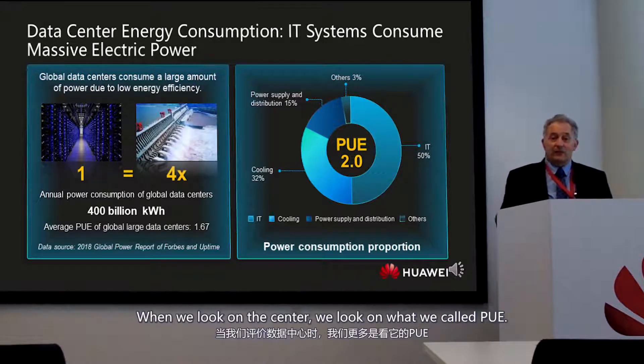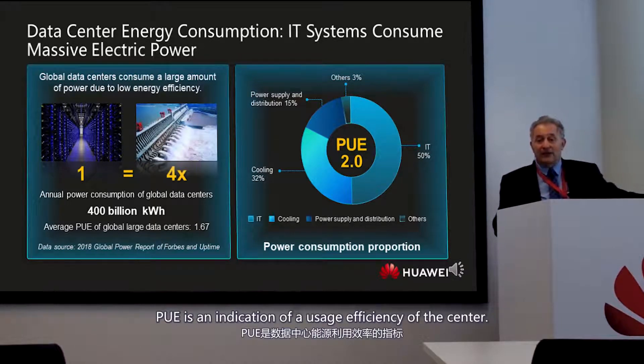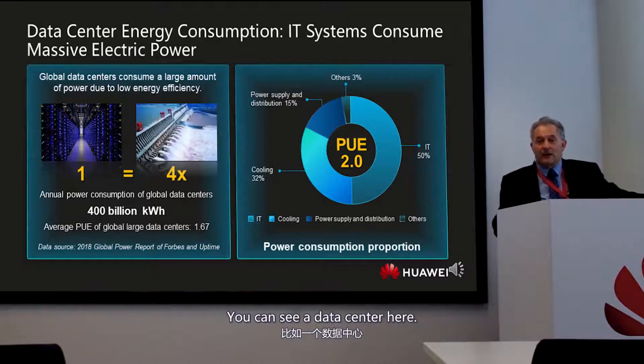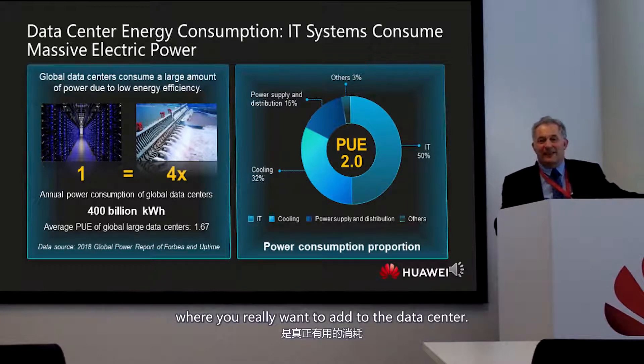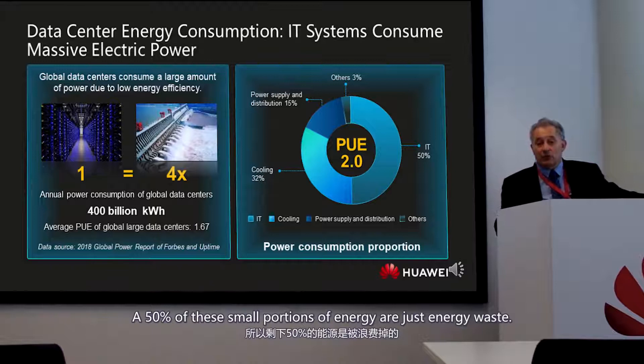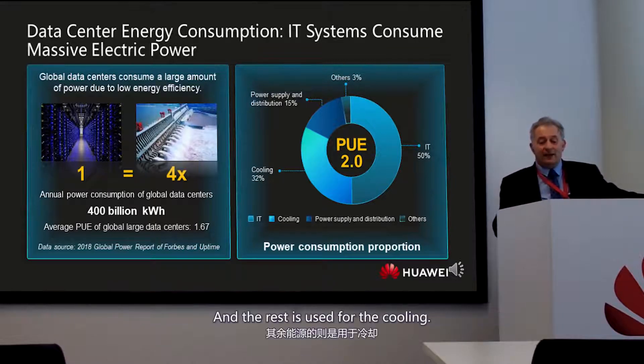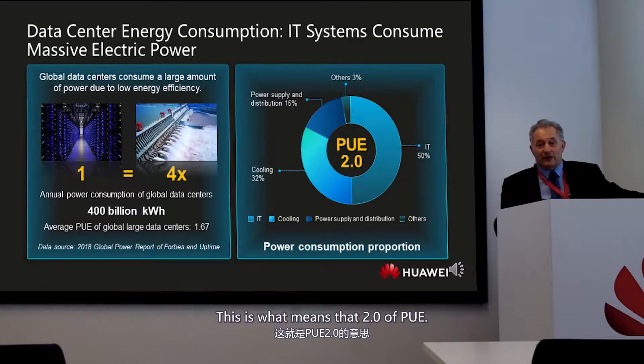What do we look at in a data center? We look at what we call PUE — Power Usage Effectiveness — an indication of energy usage efficiency. When you have a PUE of 2.0, it means that half of the energy is used by your IT load, which is what you really want. The other 50% is wasted in energy distribution. Practically, you pay for 100 and only use 50.